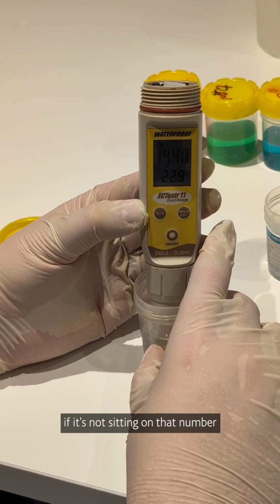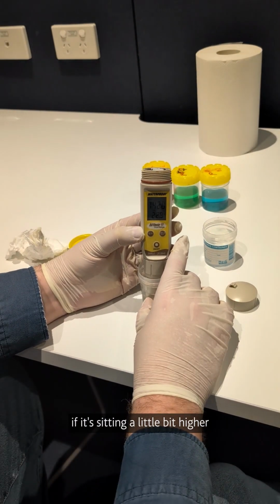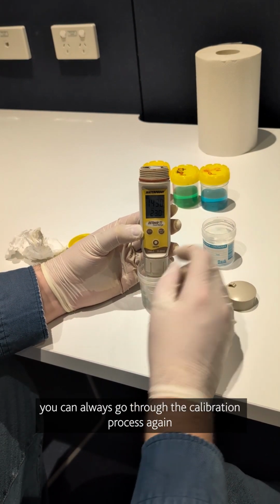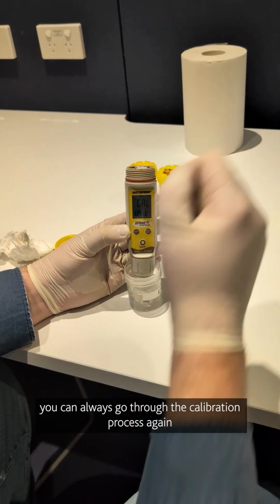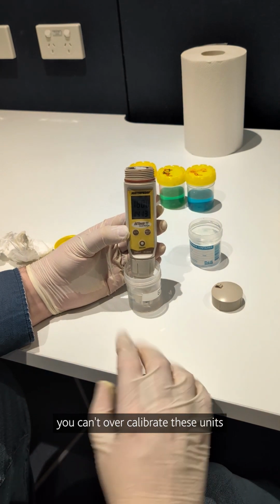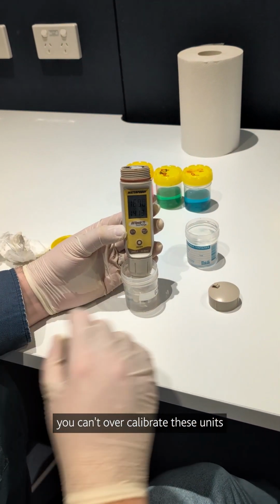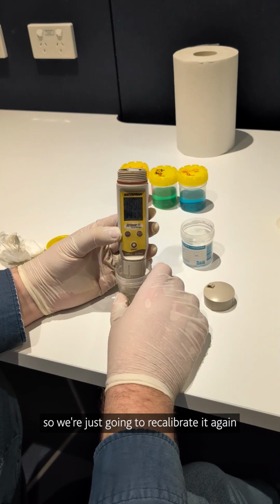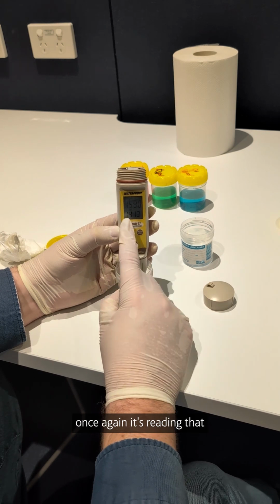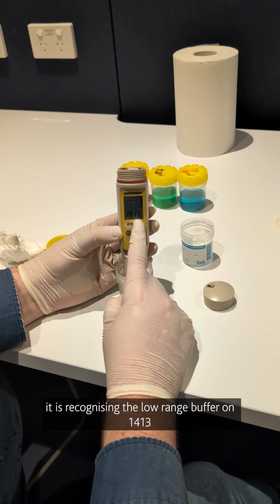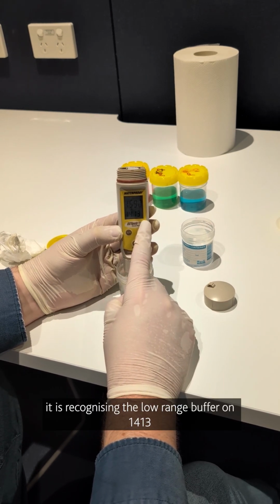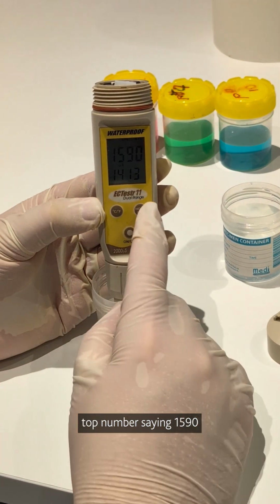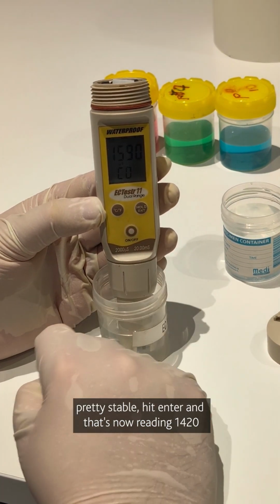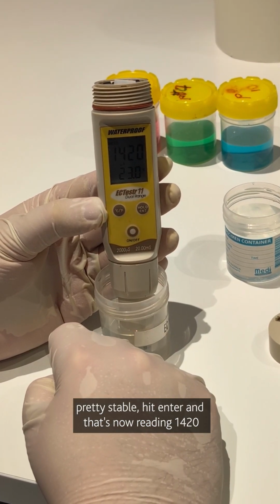If it's not sitting on that number, if it's sitting a little bit higher, a little bit lower, you can always go through the calibration process again. Here at the top, you can't over-calibrate these units. So we're just going to calibrate it again. Once again, it's recognizing the low range buffer on 1413. Top number is saying 1590, pretty stable. Hit enter, and that's now reading 1420.